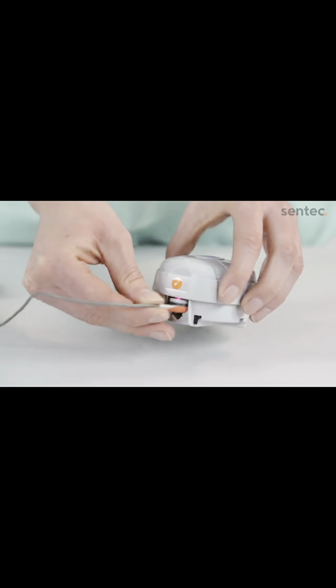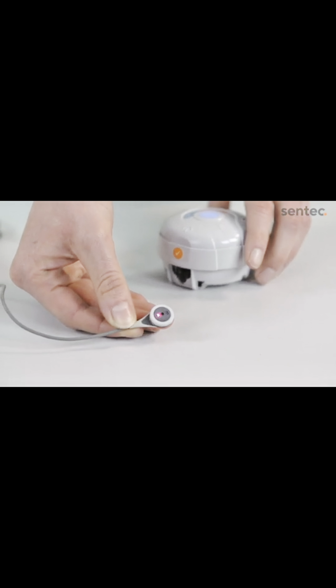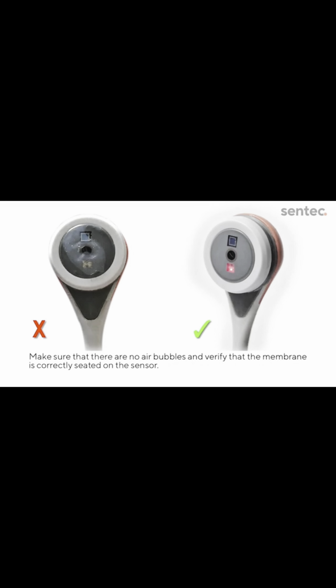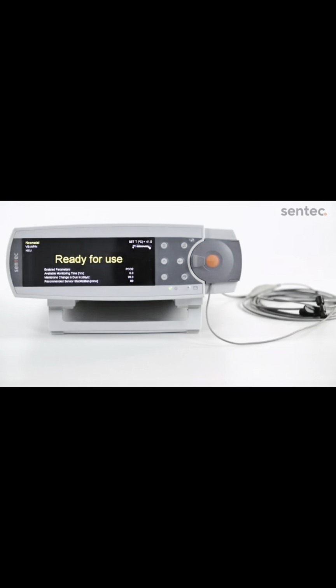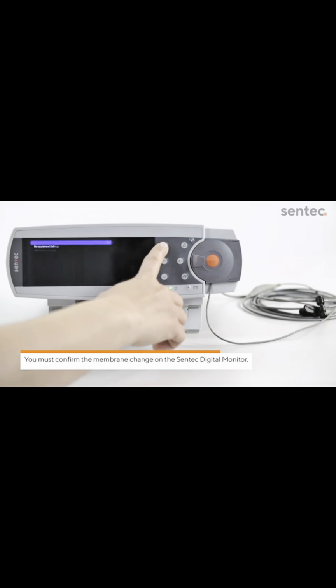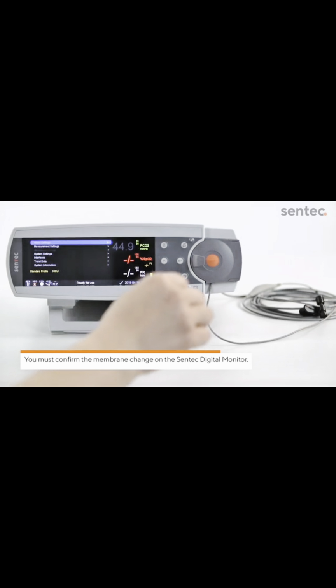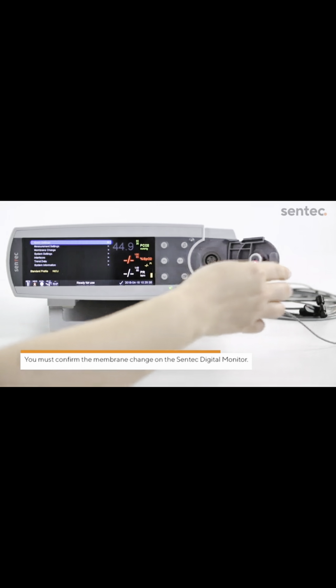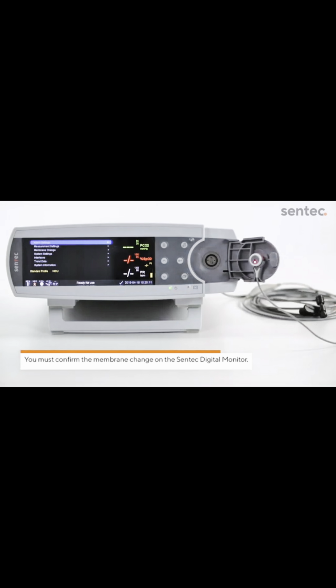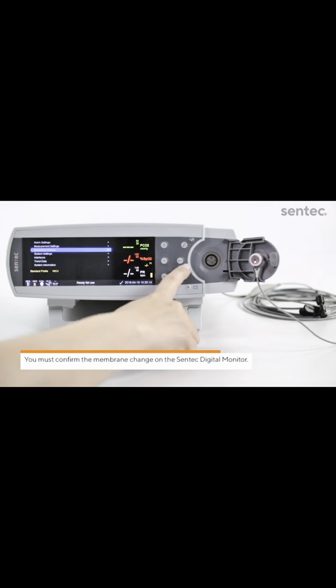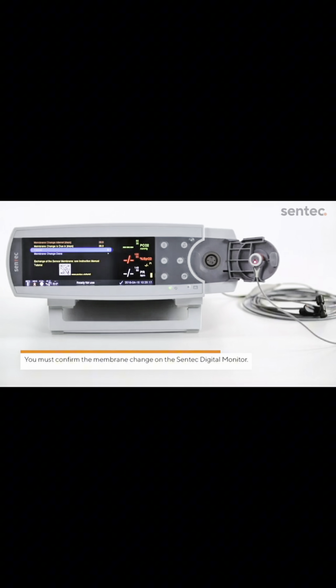Press slightly or directly lift the sensor to remove it from the membrane changer. Make sure that there are no air bubbles and verify that the membrane is correctly seated on the sensor. Before the sensor can be used, you must confirm the membrane change on the Sentec digital monitor. To do this, open the docking station door and select Membrane Change Done. This will reset the membrane change timer and initiate a mandatory calibration.